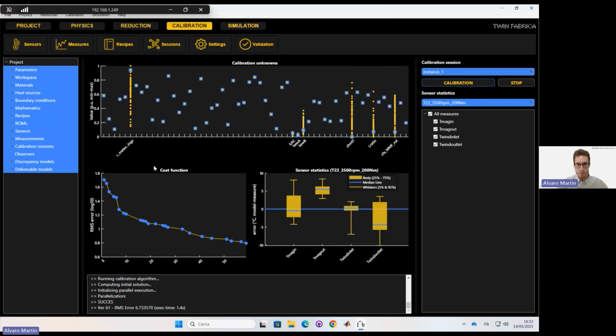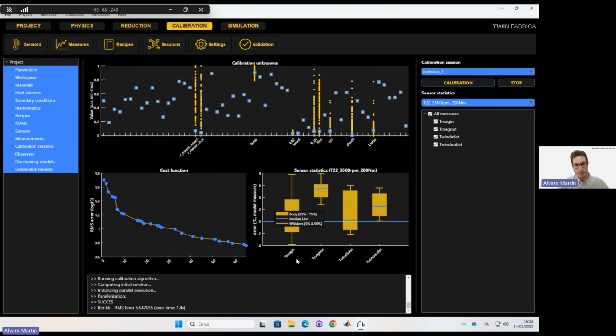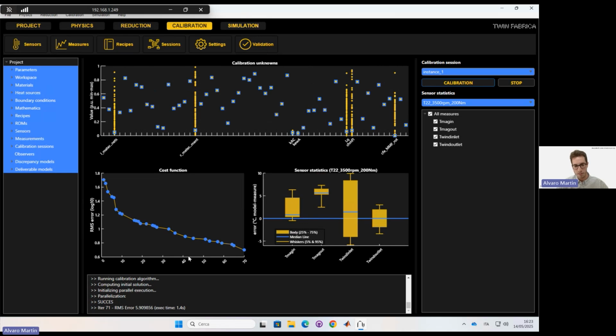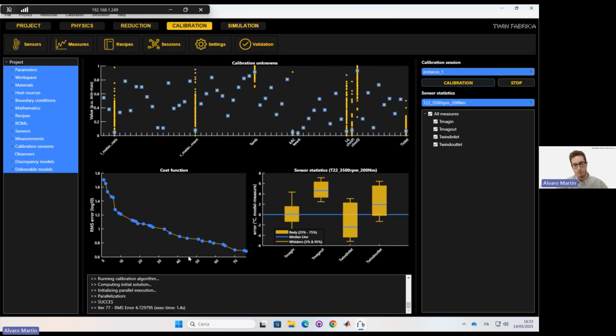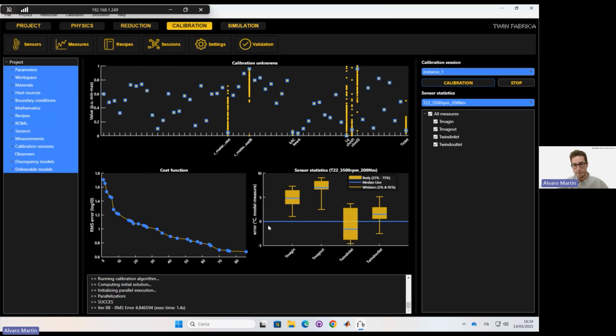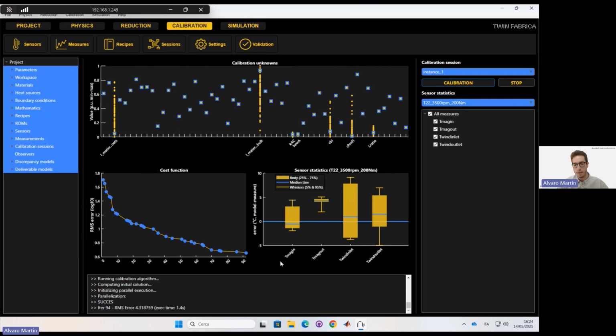As you can see on the bottom left graph, we have a cost function, which is the base-10 logarithm of the root mean square error, and it's slowly decreasing. At some point, it will come to a saturation, to a convergence, in which we will see that it's not decreasing anymore. So far, we have 70 iterations, and we still see that it's decreasing. So we can leave the calibration for, let's say, 150 or 200 iterations. On the right graph, we see some detail of the error statistics. We can see the 0 error mark here. And the goal is that all the 4 sensors that we have in the electric machine, which are the magnets and the windings, get as close as possible to the 0 error mark.